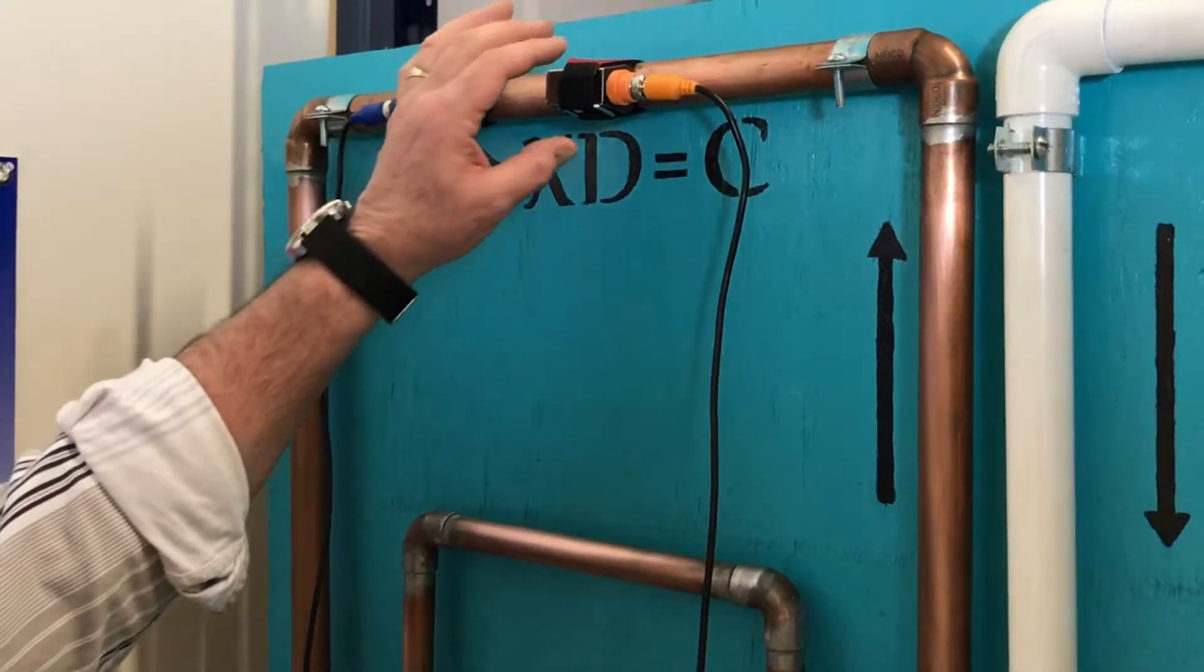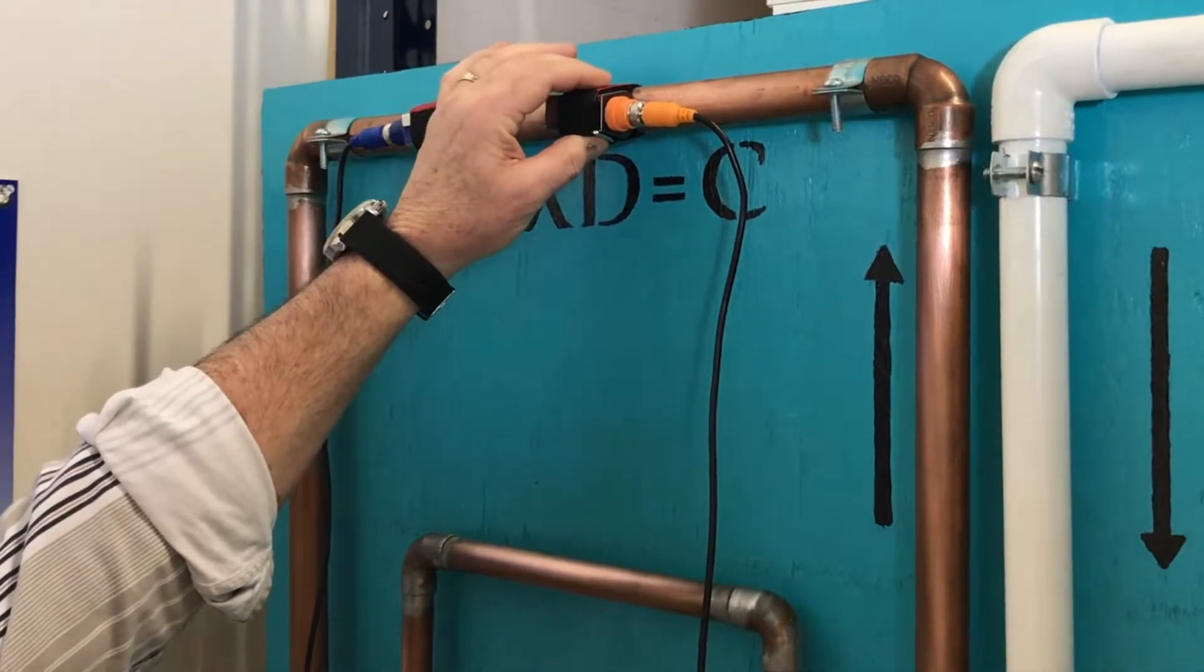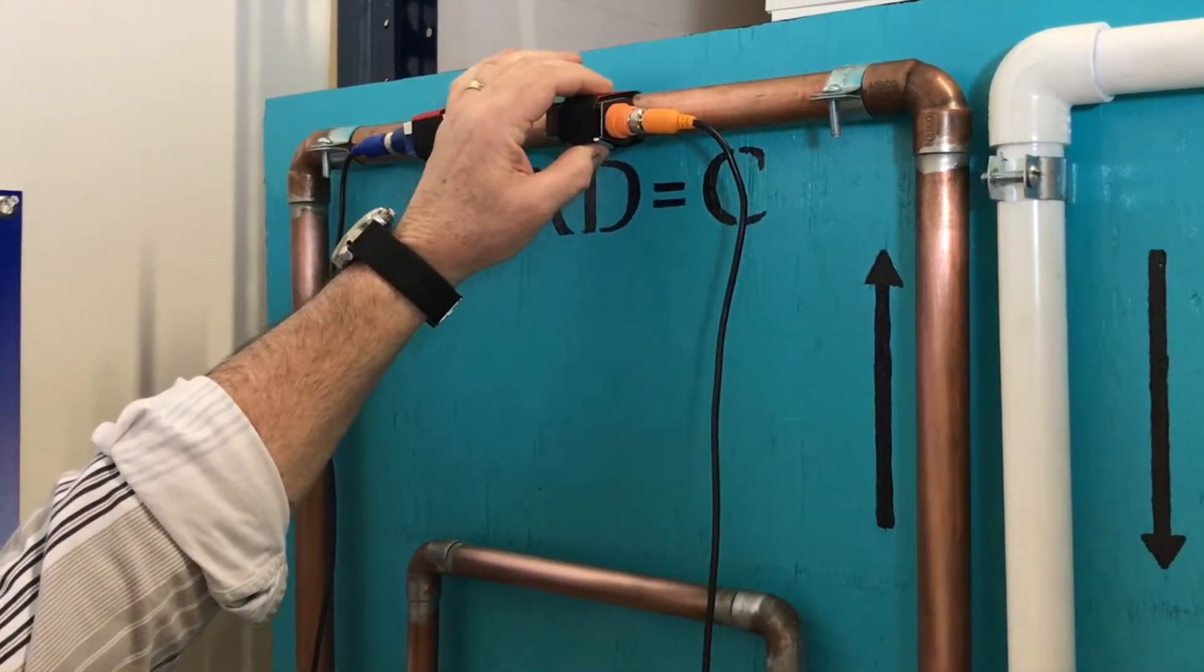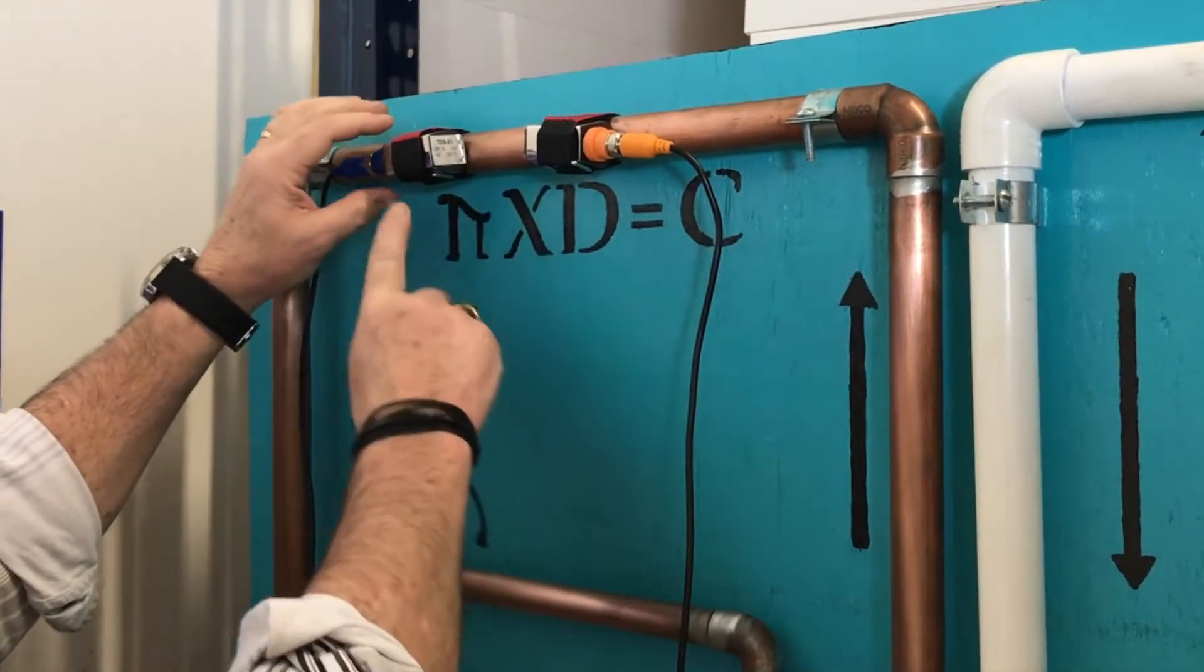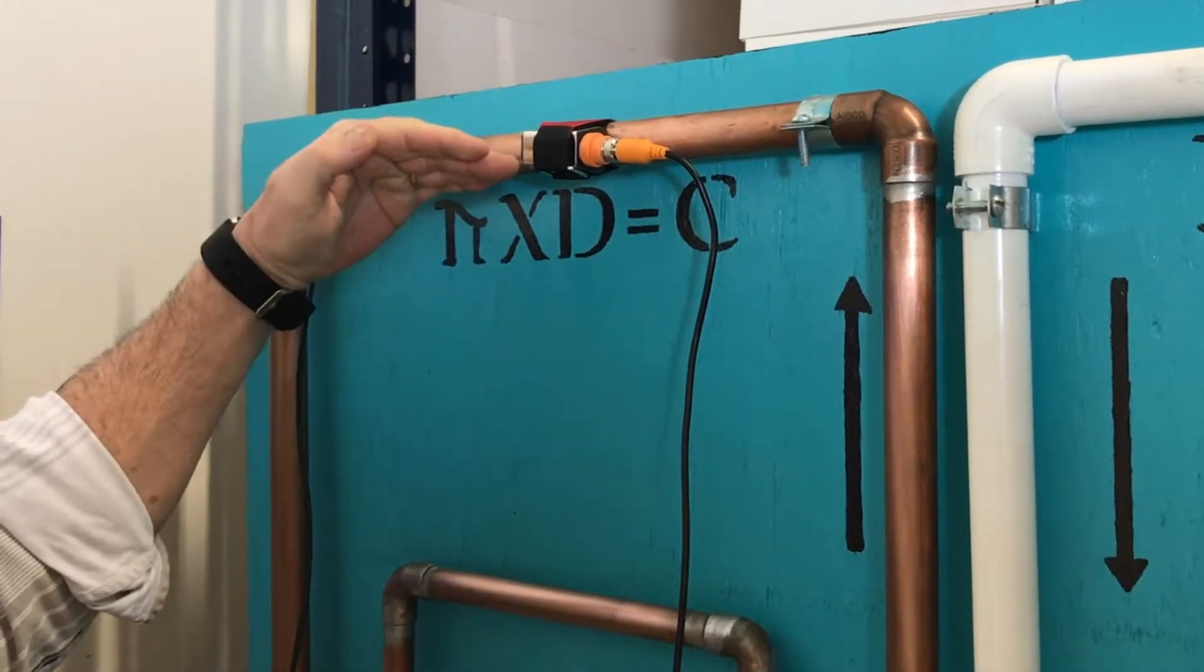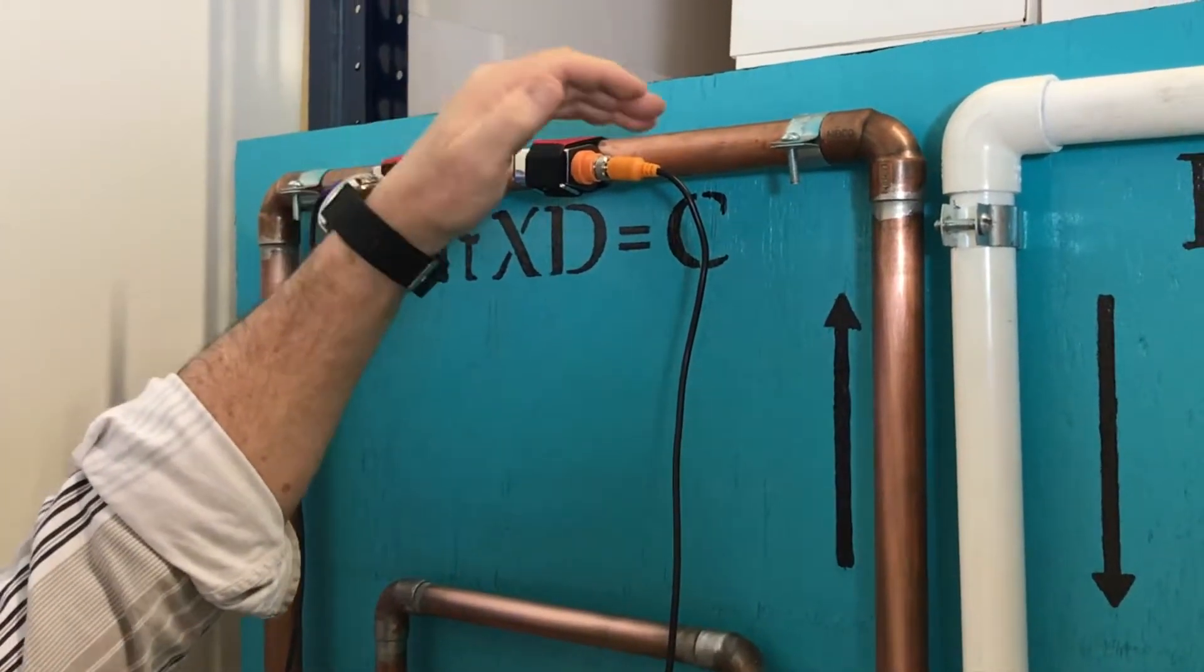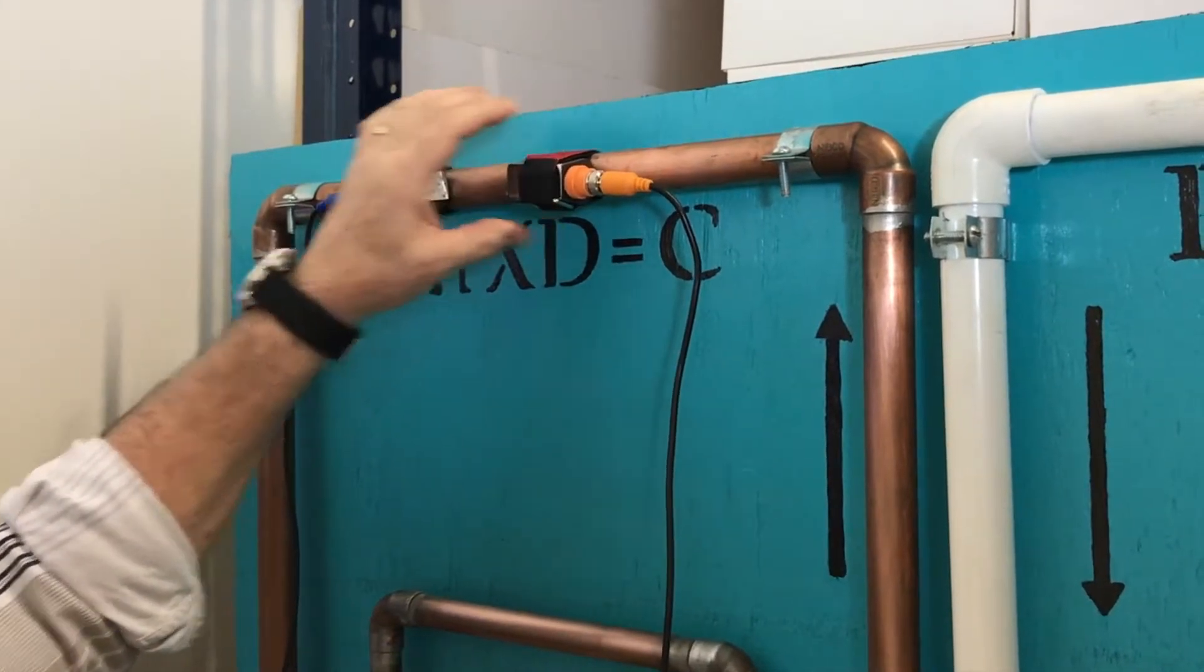When putting the sensors on, it's important to put the upflow sensor on. It's color-coded orange. This has to go in the direction of the liquid flowing through the pipe on the upflow. The blue one is the downflow sensor. Make sure they're at 90 degrees in case of turbulence or air bubbles in the top of the pipe. It will not affect the reading on your meter.